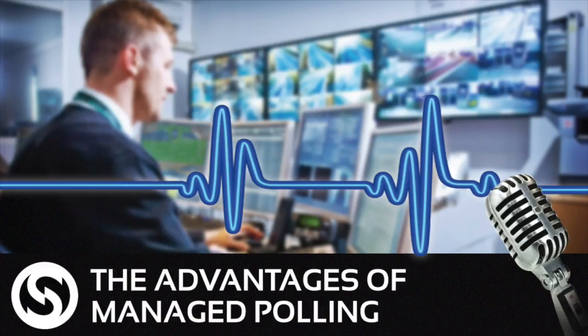I guess to clarify what Carl was saying, the point of polling is to ensure that the path is always available when the time comes to actually send an alarm event. So what we're doing is sending heartbeats or small packets of data across the network that we're going to be sending alarm events across. This ensures that we know that the network is always available, so when it does come time to send the event, the path will be there to send that alarm event across.